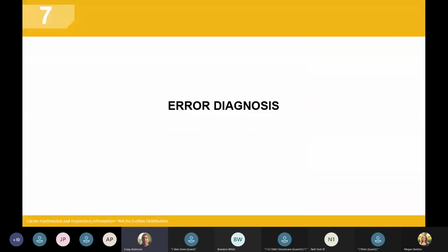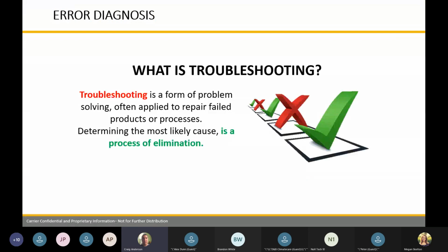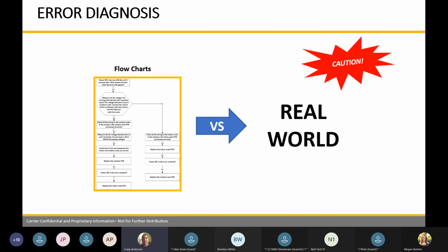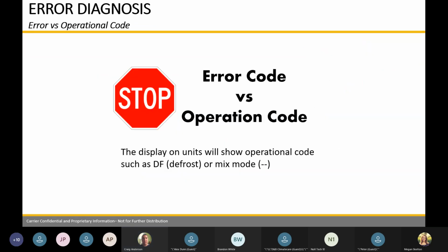So error codes, troubleshooting. With troubleshooting, we're looking for the problem. We're trying to get to the bottom of the problem to solve what the error code is, determining what the cause is, and trying to eliminate it, whether it was installation or if it was actually failure of the unit. In your manuals, you're going to get flowcharts. Flowcharts are flowcharts. They're going to bring you to the area where you should be looking. It's not going to fix the problem. It's just going to get you close. It's like an error code on a furnace. Pressure switch. We know the pressure switch failed. Now you have to figure out why.